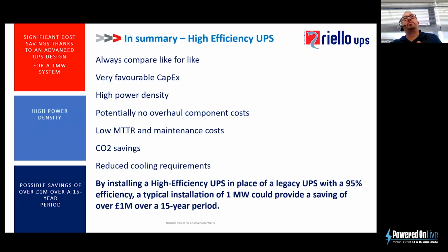So just summing it up, always compare like for like: always make sure that you're comparing an online UPS system with an online UPS system, not an average figure. It's very favorable CapEx. A typical module is probably anywhere between 7 to 12% difference compared to a standard module, so again, it's not a big difference in cost. Very high power density, potentially no overhaul component cost, low mean time to repair and maintenance costs, significant CO2 savings, reduced cooling requirements, basically by installing a high efficiency UPS in place of a legacy UPS.